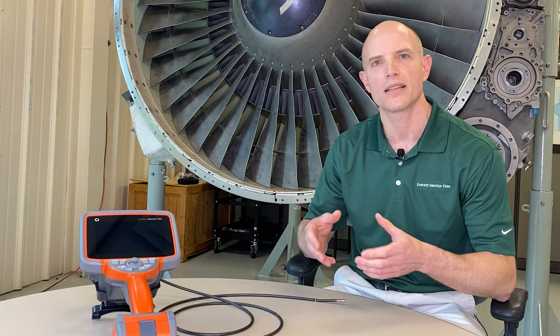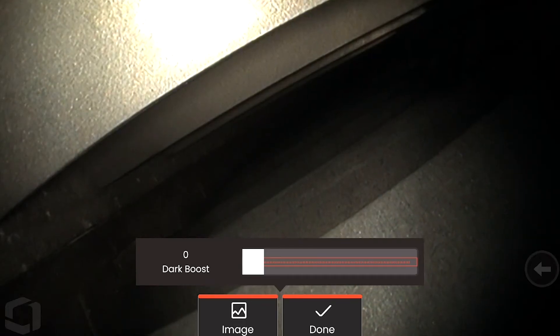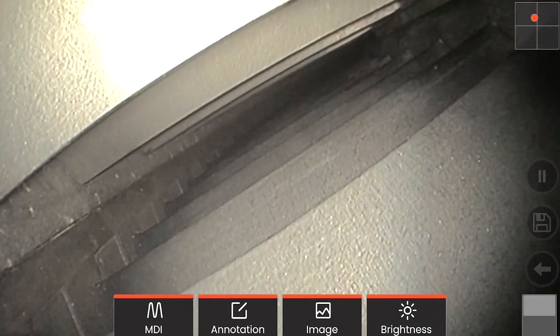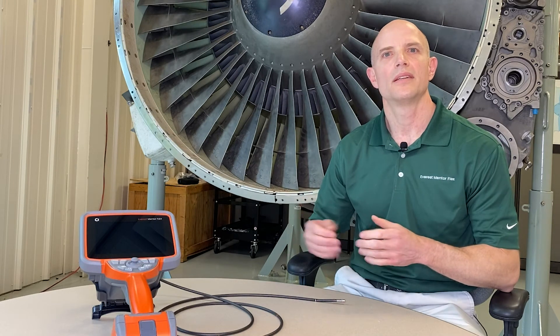But when you get into a scene where you have a lot of dark areas, possibly along with some glare — which you can often get when inspecting shiny surface objects like compressor blades in a turbine or high-purity tubing with welds — Dark Boost can lighten the areas that are otherwise quite dark without overly brightening the brighter areas. This is a new feature for this tier of product; we did not have it on our prior XL Go, XL Vu, XL Flex, and Detect products.